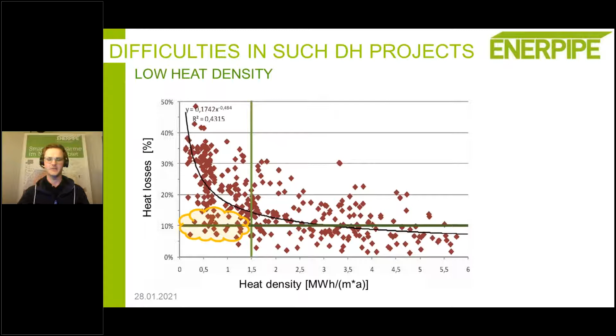But at ENERPIPE, we are quite often active in rural district heating networks on the left-hand side in this area. So we try to find solutions to get heat losses in this area to about 10%, 15%, and not higher. And there we have developed different kinds of solutions. There's just one thing which quite often helps in such projects, and that is to have in each house not a standard heat interface unit. Quite often we use, in this case, decentralized buffer tanks.